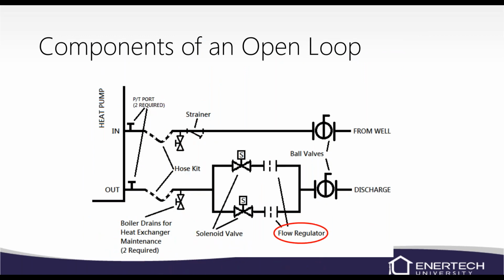Open loop, these are the components that we're going to be using on an open loop system. We don't just want to run water through the system all the time. You're going to be wasting a lot of water. You could deplete your well. So make sure we have a shutoff valve after your well pump. Always put a strainer in so we can collect any sand or debris before it gets to the unit. Make sure we're putting a shutoff there as well so we can isolate and clean out that strainer. Make sure you're putting pressure temperature ports in on the in and the out. Again, put a boiler drain on the outlet so that we can clean that heat exchanger. Over time, it will scale up, and there's a calculation we can do to figure that out. And then once we know that it's dirty, we can actually clean it out through those boiler drains.